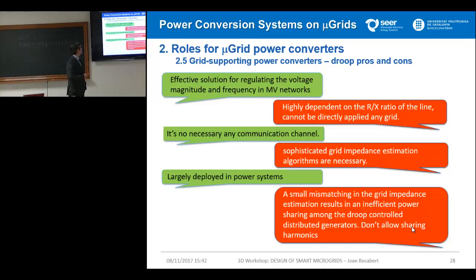advantages and disadvantages of the droop curves. Okay, the droop curves are a very effective solution to regulate the voltage magnitude in medium voltage networks. Medium voltage because it's the inductive line it's imposing. The problem is that it's highly dependent on the R/X ratio. Okay. So the advantage is that it's not necessary to have any communication channel to apply some equilibrium point. It's very good, okay? It doesn't depend on communications, at least to get the primary, working operating point. The trade-off is that you need a sophisticated grid impedance estimation algorithm, okay?